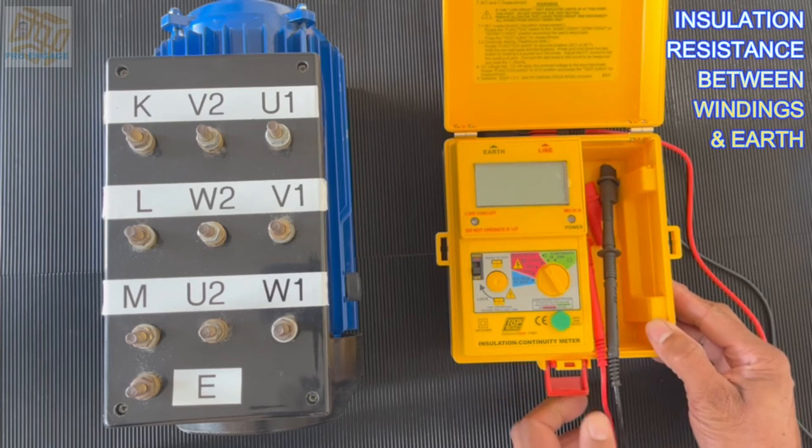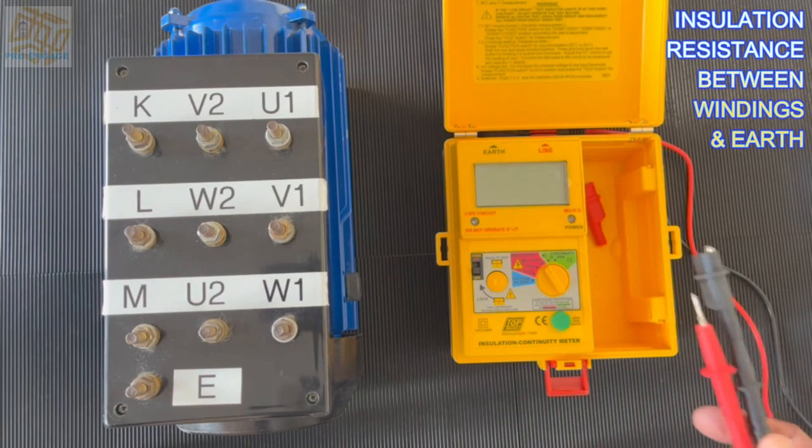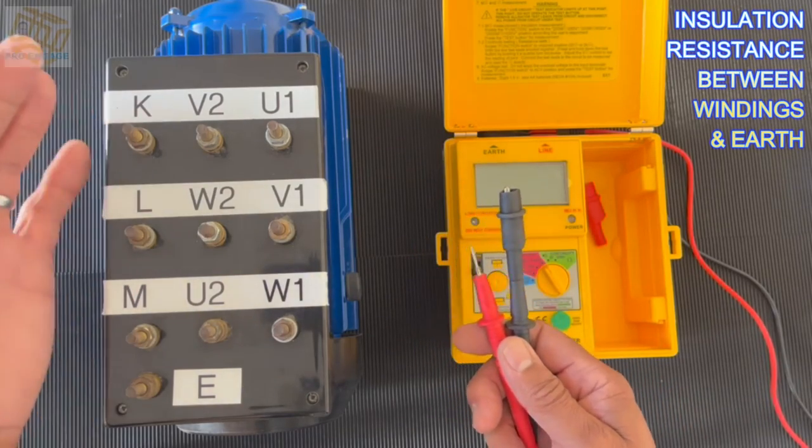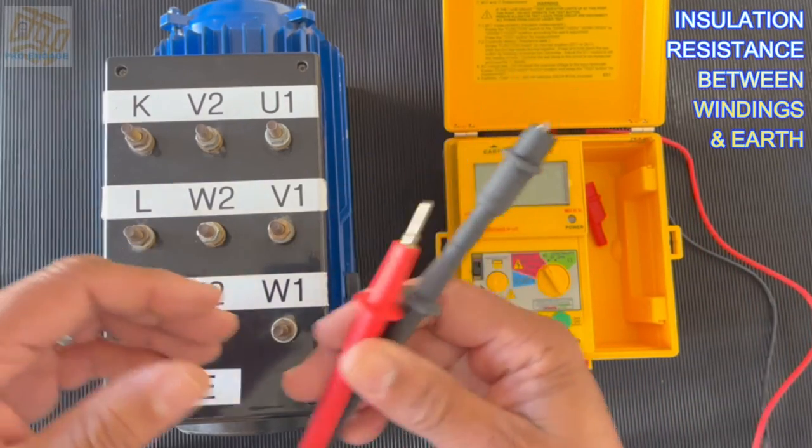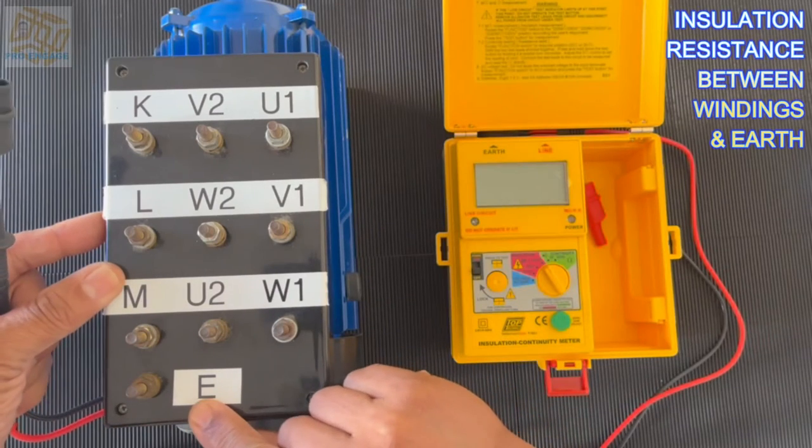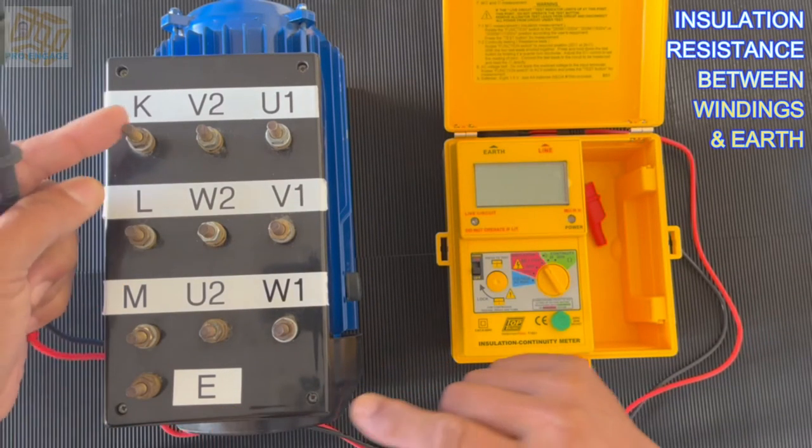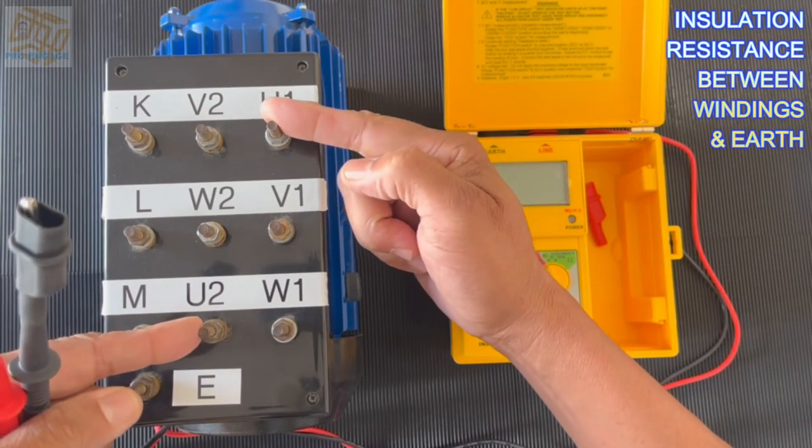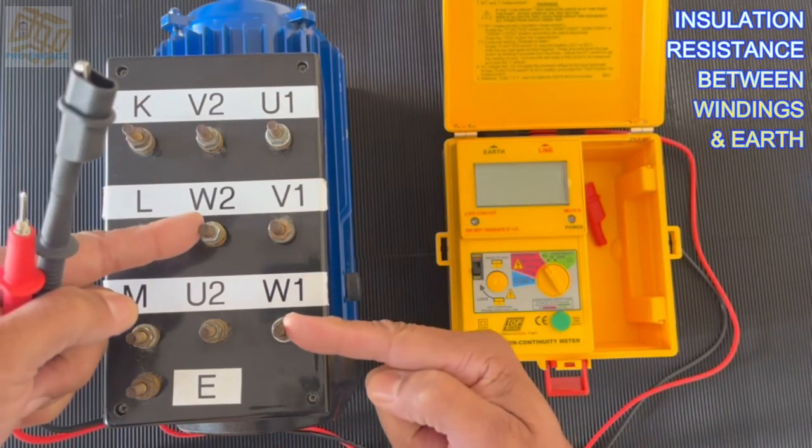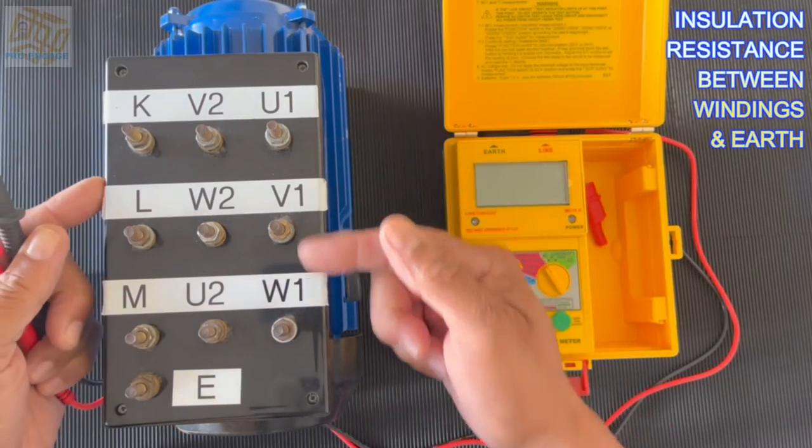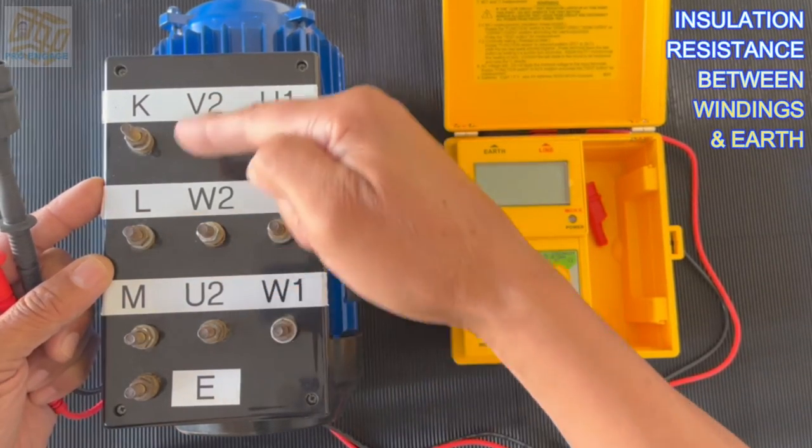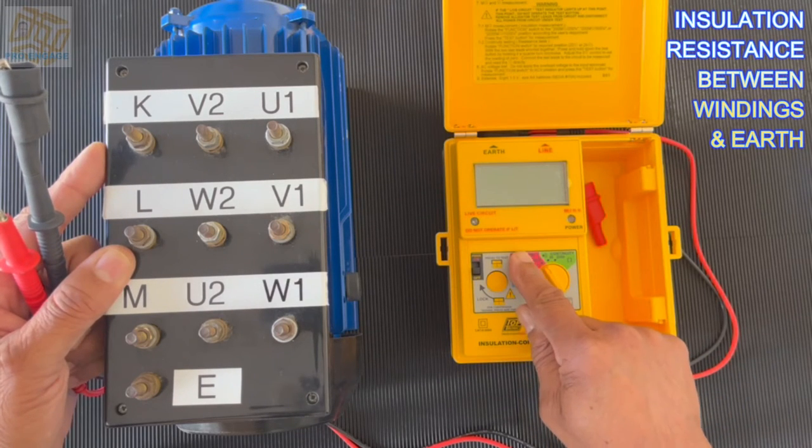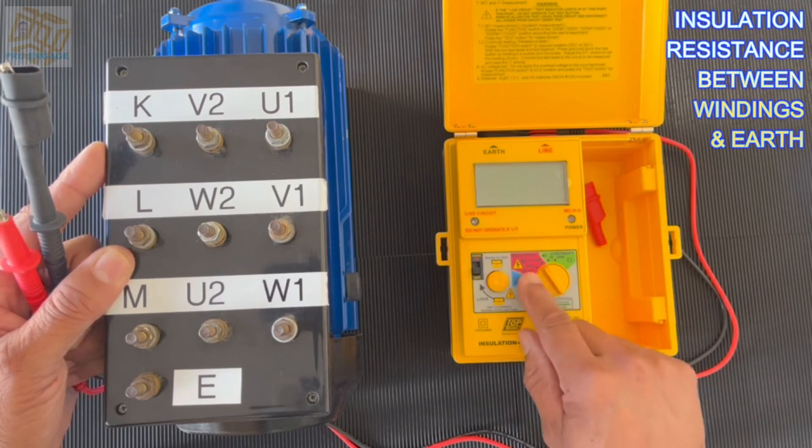And just for interest sake, we want to just have a look at the digital tester to see if it does the exact same thing. And so we will do the same test again. Same motor, we want to do earth to all the windings. We've identified the windings as per our continuity of windings test. We know where our windings are and we're not going to do the center. We will do only the far left and the far right.